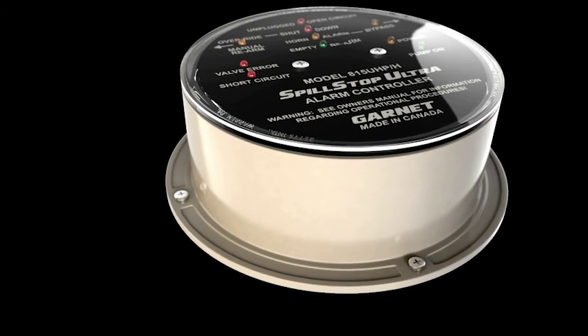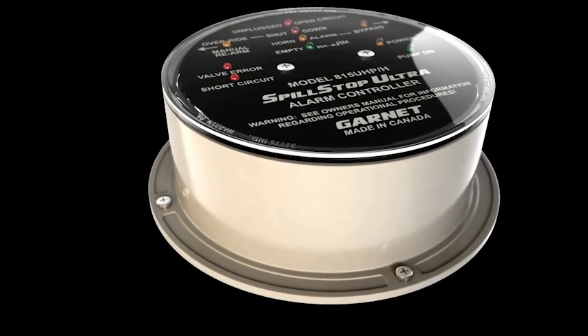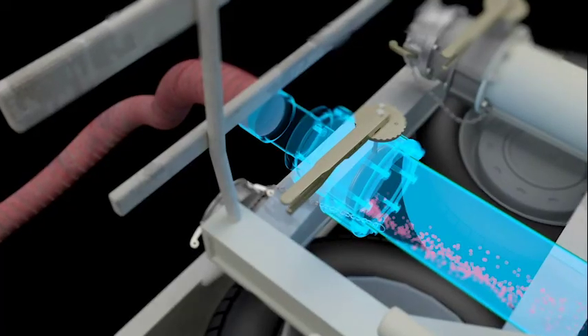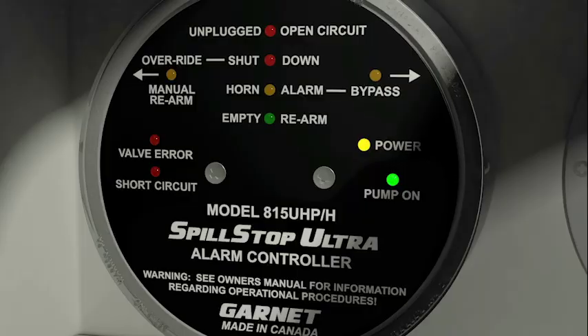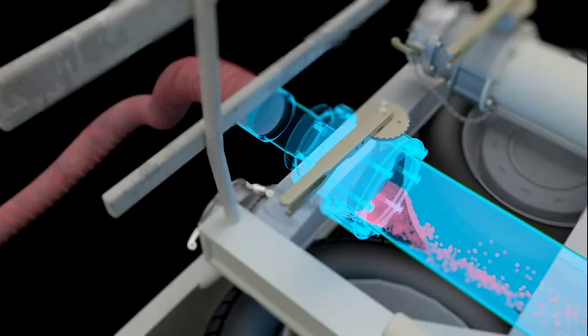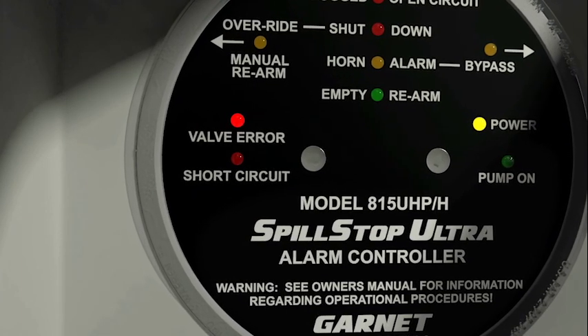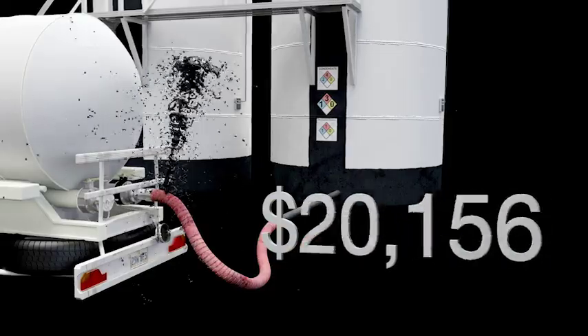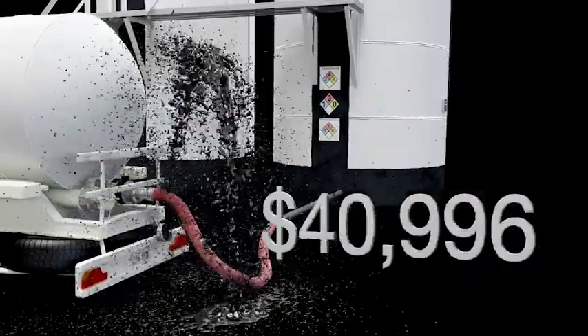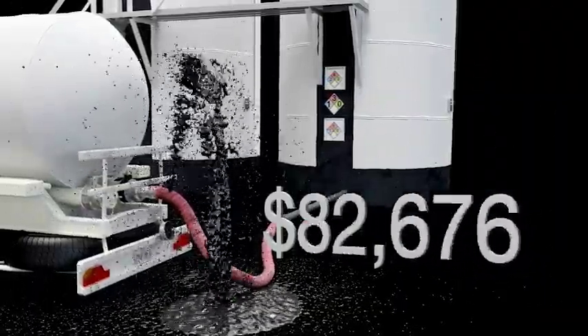The 815 UHP Spill Stop Ultra is also equipped with new safety features. During the loading and unloading process, if a valve is closed, the pressure sensor will detect the overpressure condition, shut down the pump to prevent damage from blown hoses, and activate the valve error indicator on the display. This feature helps prevent spills from blown hoses that cost high enough to seriously inhibit the profits of the trucking company.